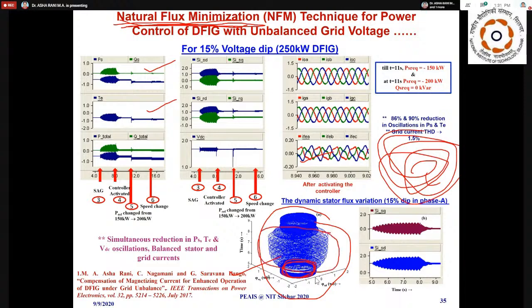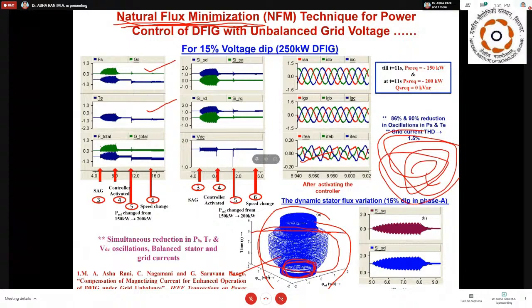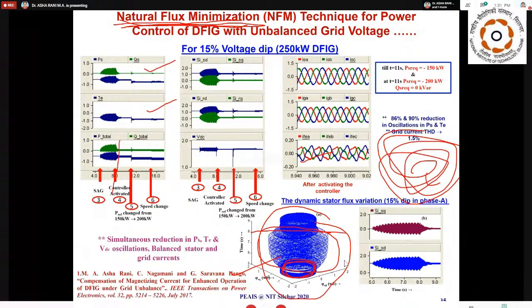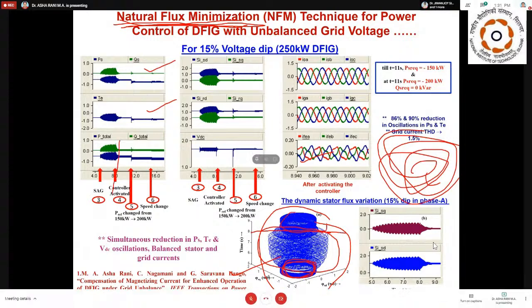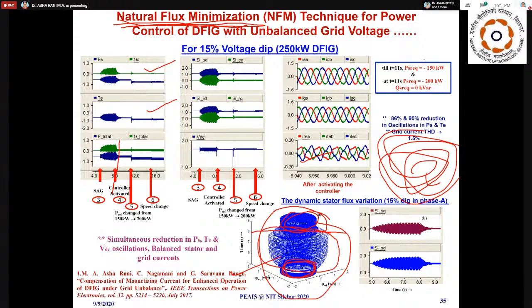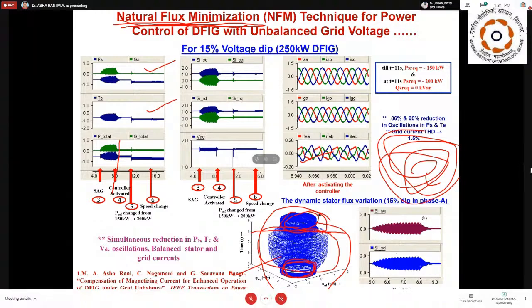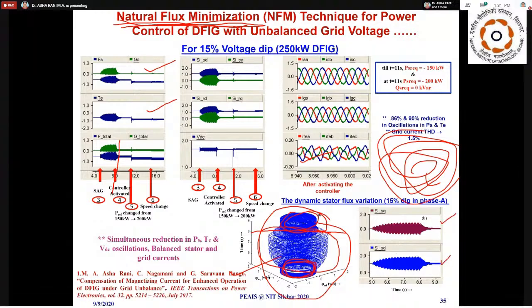You can see clearly from 8 seconds when we turn on our controller, it becomes balanced again. How it becomes balanced is by this methodology - we are injecting currents in such a way that it produces a negative sequence flux which damps the additional flux rotating inside the machine, so the flux comes back to 0.